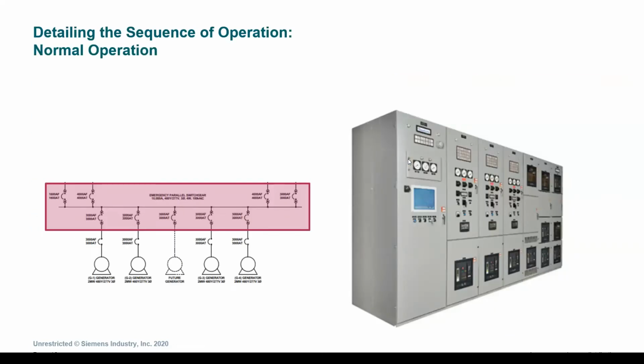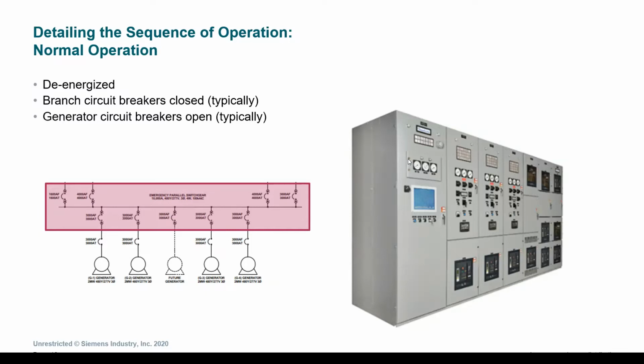So first, looking at the sequence of operation in the normal mode, the equipment operates de-energized. The branch circuit breakers will be closed and the generator circuit breakers will be open. And again, this is the regular operation of the equipment as it stands in a ready state for a normal source power loss. So now we're going to look at how the equipment reacts when that loss of normal power happens.